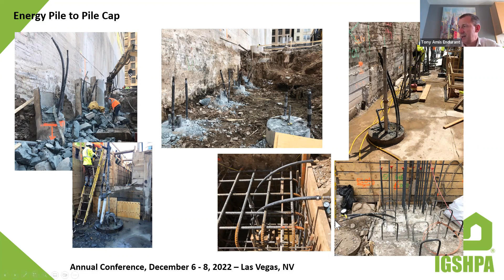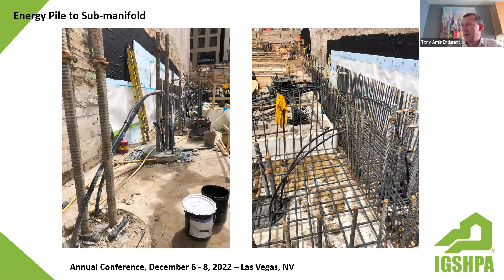Now this would be a significant hold point. So before the piling contractor is allowed to form and pour concrete in this particular case, we would say we need to do a flow test and a pressure test. You can see the pressure gauge at each of the key stages. We're monitoring the loops, they're filled with water at this stage, and there's a regular check to make sure that there's no drop in pressure as work proceeds.